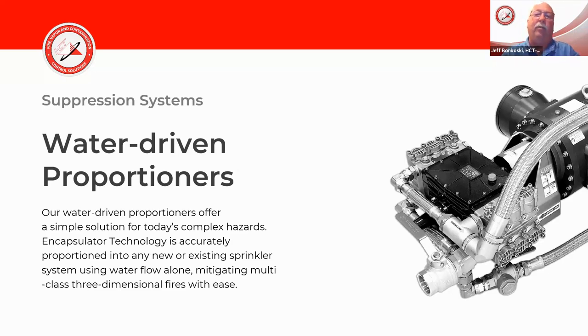As far as the maintenance, when you have to do your annual testing with those bladder tank systems, you have to get a frac tank, or something there to catch that water runoff so that you can collect it and haul it off. Yet with the water-driven proportioner, you can basically run the system. You can take the concentrate and have it go back into a bucket and reclaim it, and be able to check the system without having waste, and do your calculations making certain that it's flowing at the correct percentages.